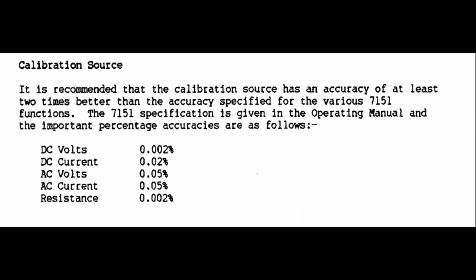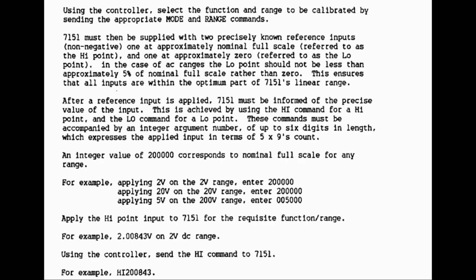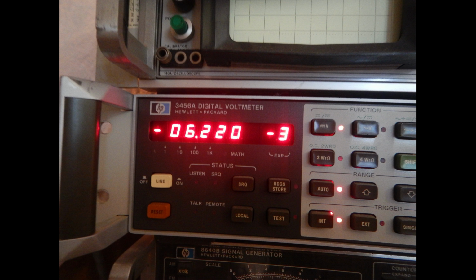However, to calibrate a multimeter, we need a device that can supply accurate and stable voltages and currents, and that's something I don't have. Luckily, the calibration of this multimeter doesn't require exact voltage values, as long as they are stable and can be measured with another similar or better multimeter. In fact, I have an HP 3456A bench multimeter that I can use to compare the readings. Of course, even this instrument may be out of calibration, but at least it never required any work in the analog part, and most importantly, I cannot think about any alternative method with what I have at home.